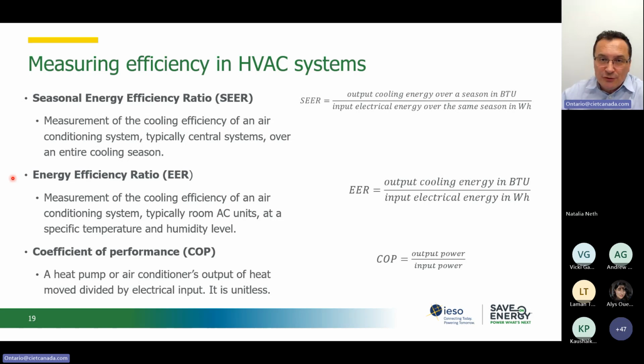So to avoid confusion, some manufacturers just completely forget about showing the units and they just show you a number. So EER 22 or EER 15, that's what we see on the equipment, or SEER, as a matter of fact. But we know that behind that there is actually a unit, and it's a different unit for the numerator versus the denominator. For larger equipment, or if you want to avoid this confusion with the units of measurement, we refer to a coefficient of performance, which expresses both the numerator and the denominator in the formula using the same units of measurement.